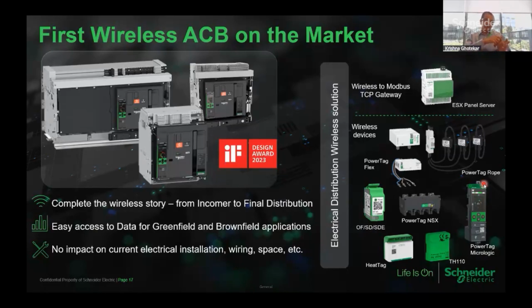So that means without adding any cable, anything, you just add on a PAS gateway. It will add on not only the high-end trip unit with power measurement, frequency, with ERMS, contact wear, plus also wireless connectivity to the PAS gateway. So for brownfield applications, it's much more important features.